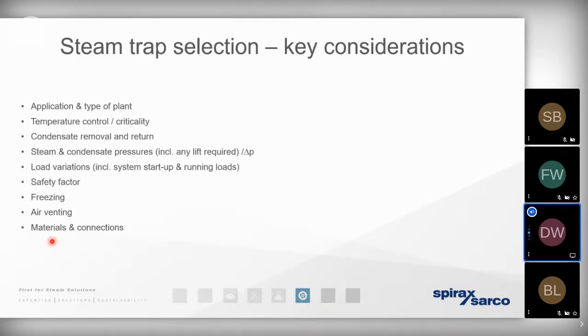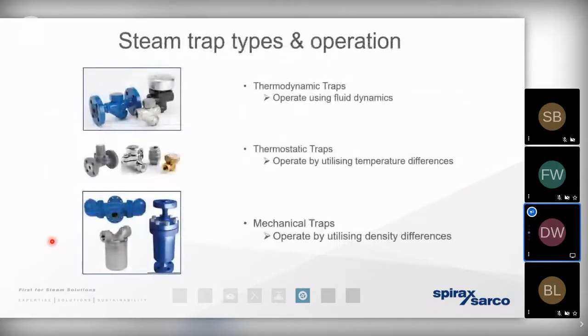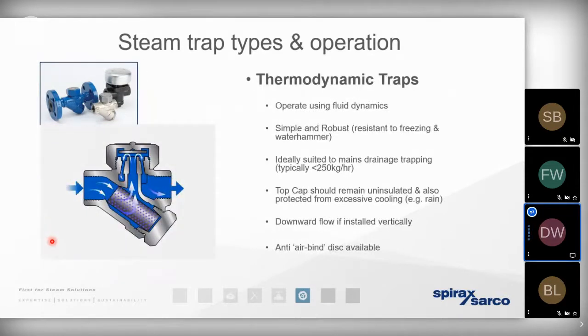So the basic steam trap types will operate in a number of different ways, and they fall into one of three different categories. We've got the thermodynamic traps, we've got the thermostatic traps, and we've got the mechanical traps. So looking very quickly at each of these types in turn, first and foremost, we've got the thermodynamic or TD trap.